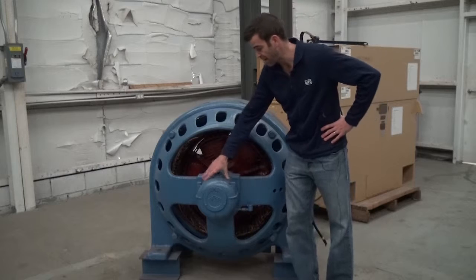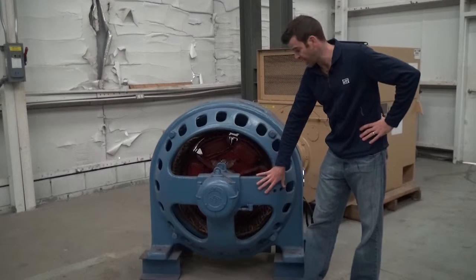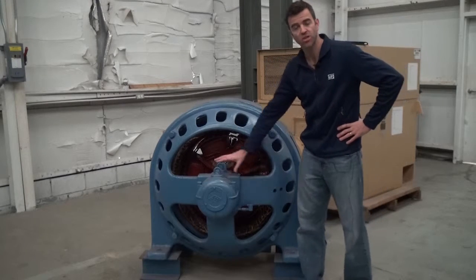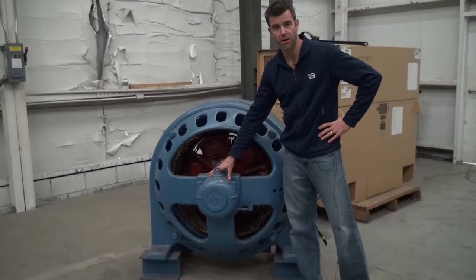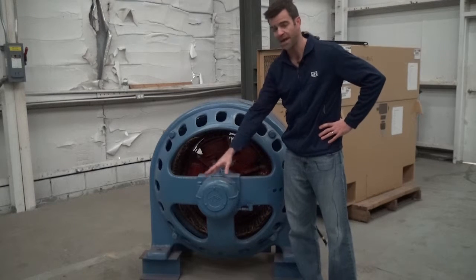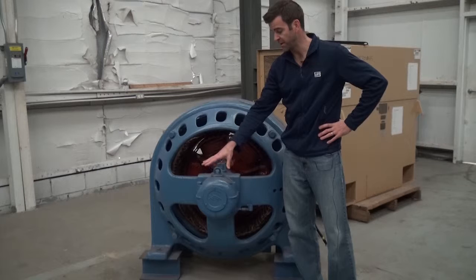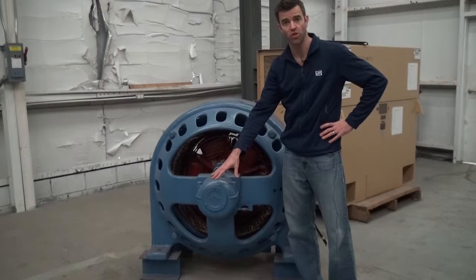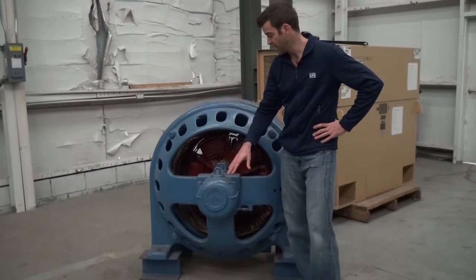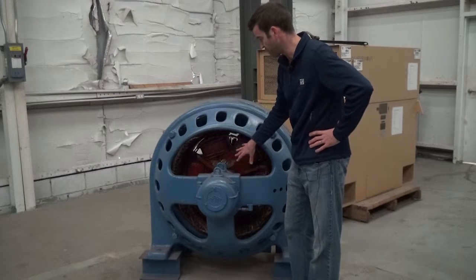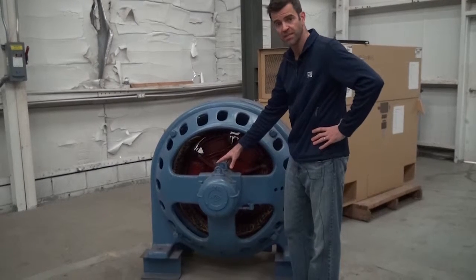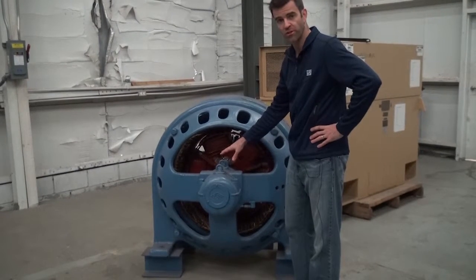You can see that the bearing assembly is mounted on the end of the motor via a bracket. So this would be called a bracket-mounted bearing. This is in contrast to a pedestal mount bearing, where the bearing is located externally on its own pedestal and sole plate. Within the motor, we have a number of different components, and within the bearing assembly, and we'll talk about those in greater detail now.